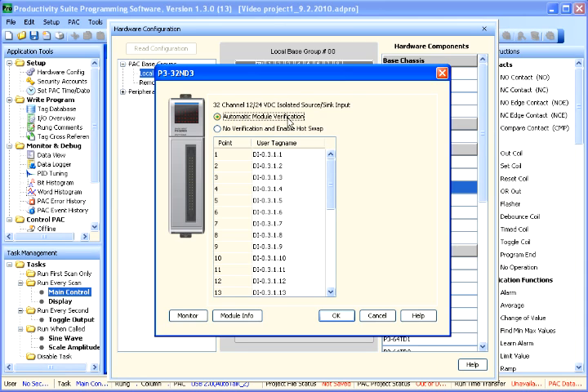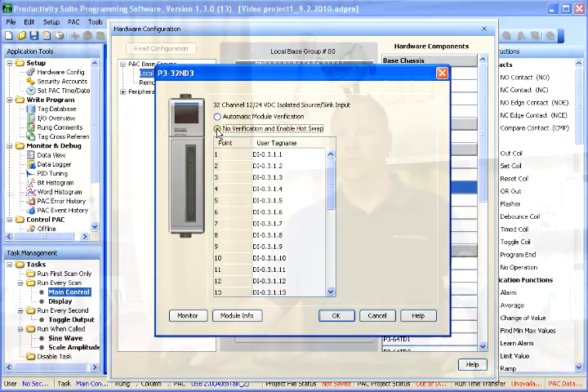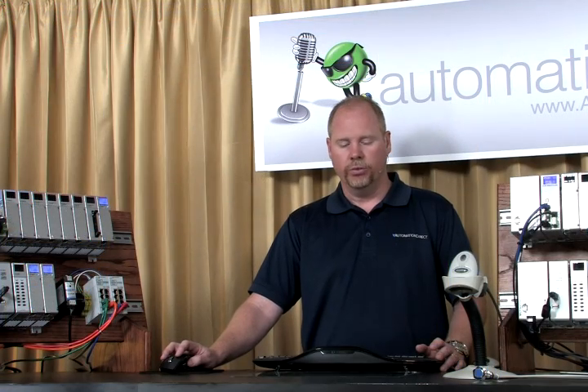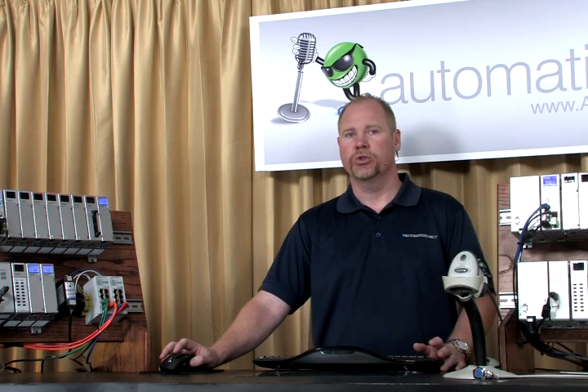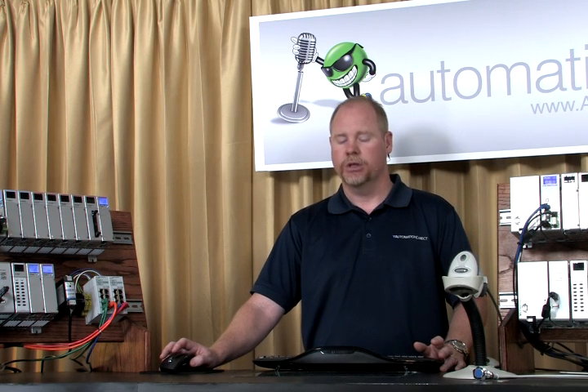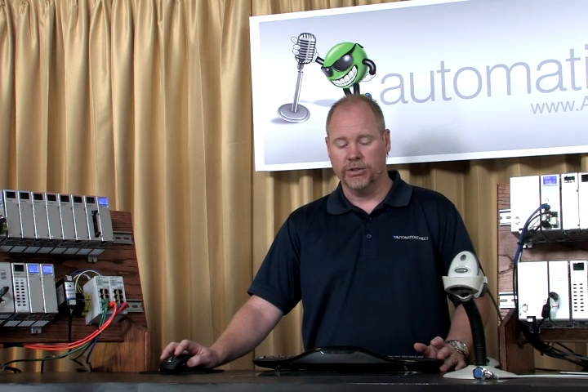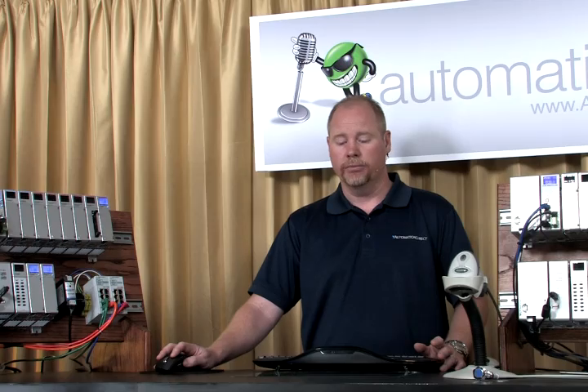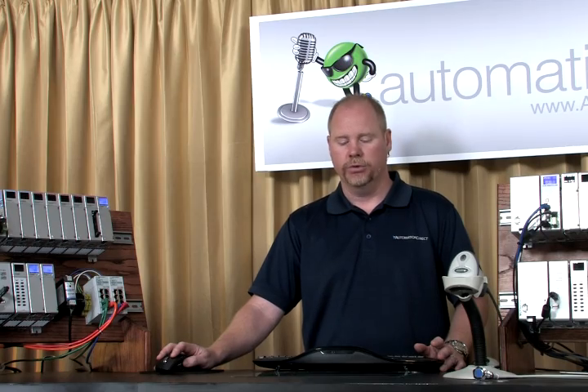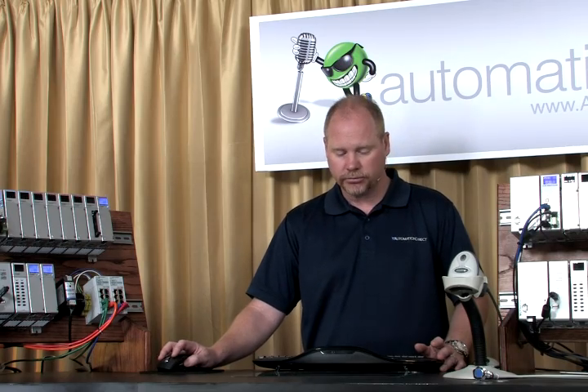These modules are automatically set up by default to be automatic module verification. This means that if your hardware configuration changes at any time, it will give you an error. If you want this to be hot-swappable, you can select the no verification and enable hot-swap. This will allow you to remove the module during operation without shutting the system down. It aids you in troubleshooting for systems that are extremely sensitive to being powered off or shut down.